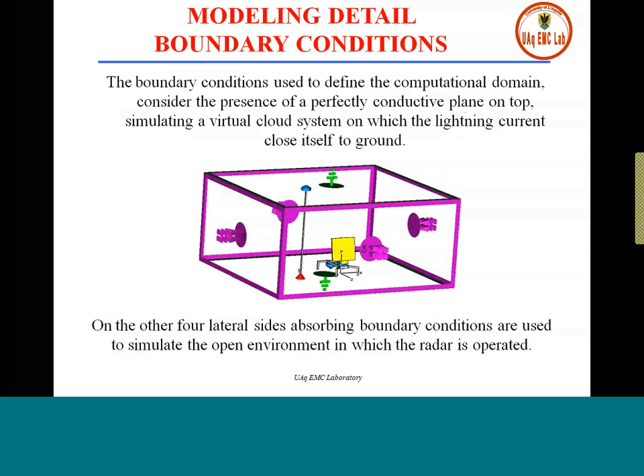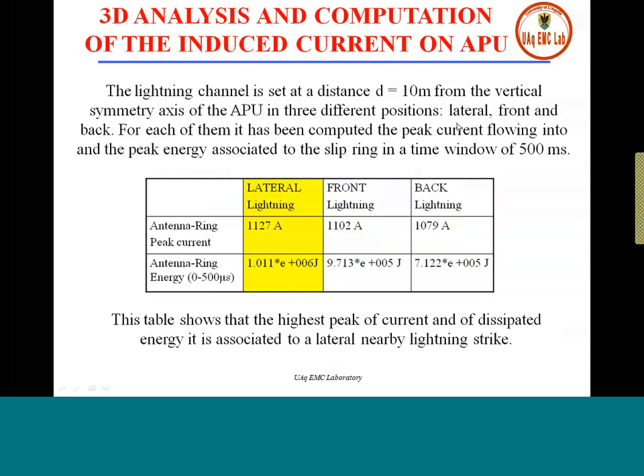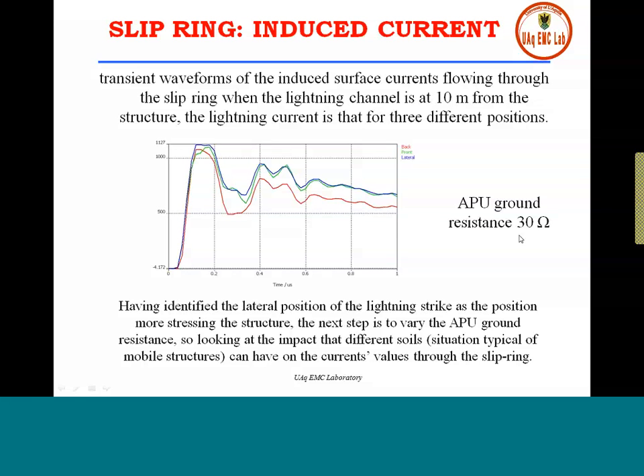Different cases are studied: what happens if the lightning strike occurs laterally, in front, or at the back of the radar. Using CST Microwave Studio, the peak current in the slip ring was evaluated. We see that the peak current occurs for lightning strokes that happen lateral to the radar system. Here you see the waveforms: black is back lightning, red is front lightning, and blue — lateral — is where we find the maximum current in the slip ring.